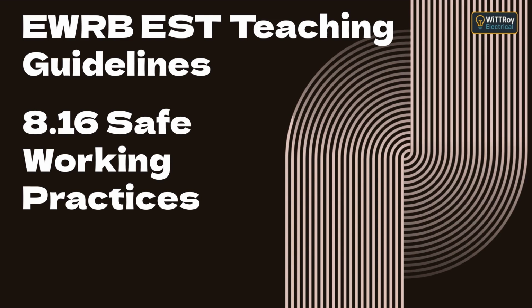Topic A, the meaning of safe working practices. Safe working practices mean using methods that control risk and prevent harm while performing electrical tasks. It's not just common sense, it's a requirement under AS/NZS 4836 and Regulation 13 of the Electricity (Safety) Regulations 2010, which states that all electrical work must be carried out safely. Safe work means more than just turning the power off. It means assessing hazards, planning your steps, isolating correctly, proving dead, and using proper tools and protective gear. Every job, from replacing a light fitting to servicing a motor, must follow the same structured safety process.